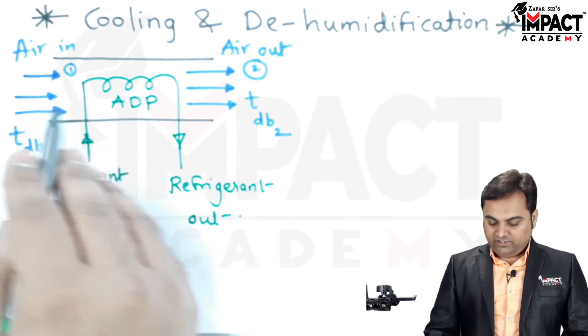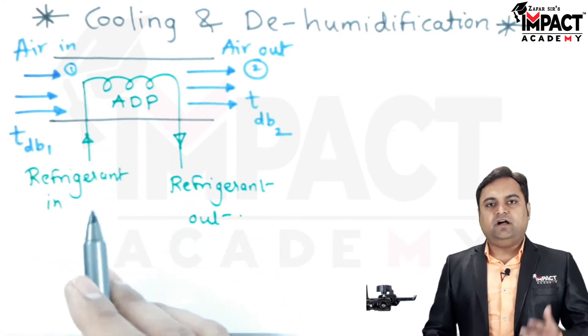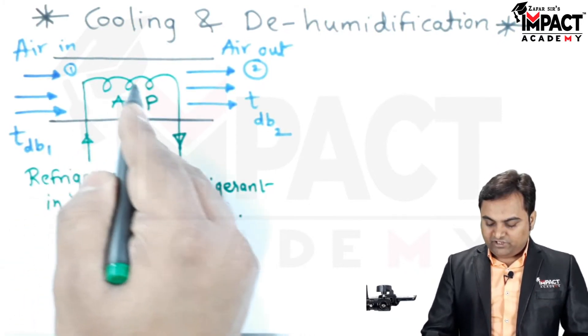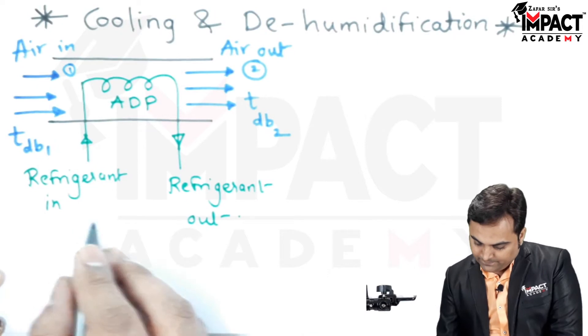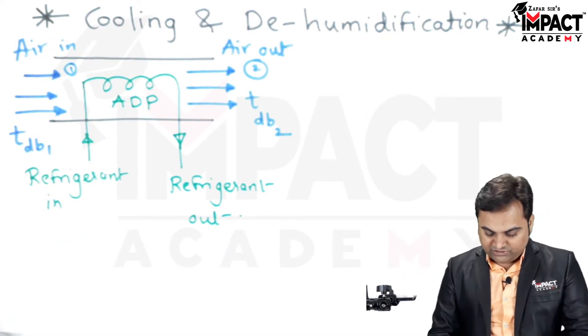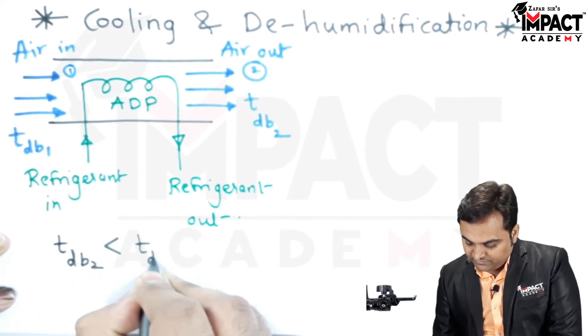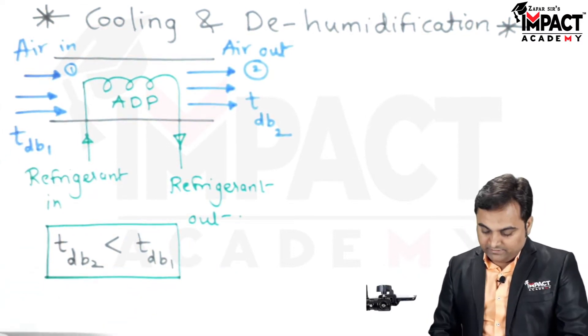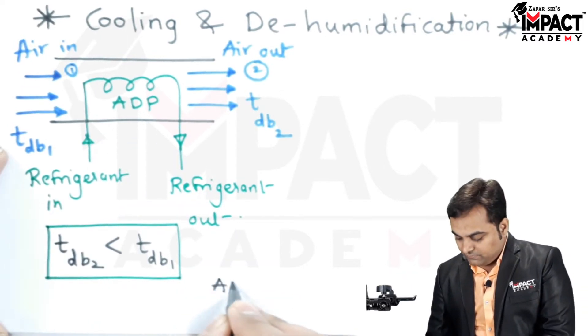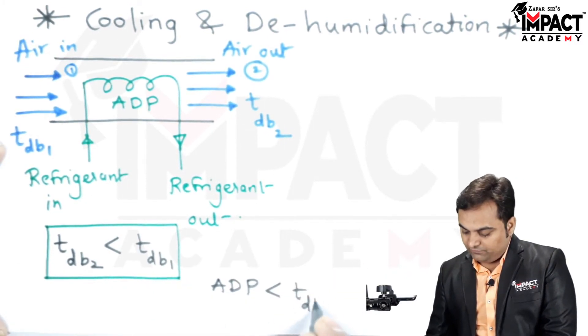What happens here is that the moisture present in the air would be condensed, and in this way the amount of moisture in the air is reduced — that is dehumidification. At the same time we are cooling this air, so the process is cooling and dehumidification. We can say that the dry bulb temperature of the air which is leaving, Tdb2, is less than Tdb1 of the entering air, and the apparatus dew point temperature of the cooling coil is less than the dry bulb temperature of the exit air.